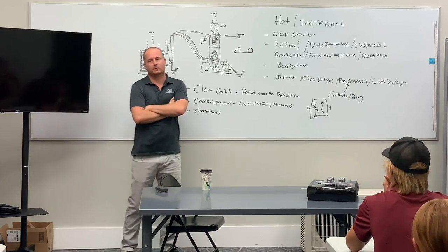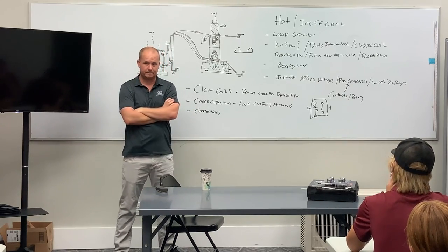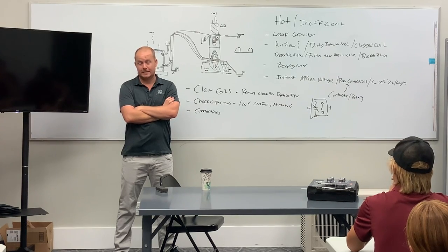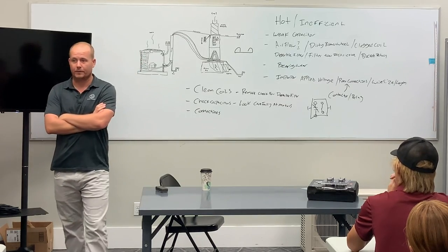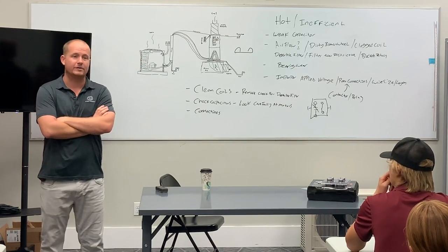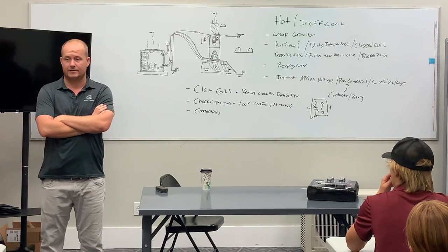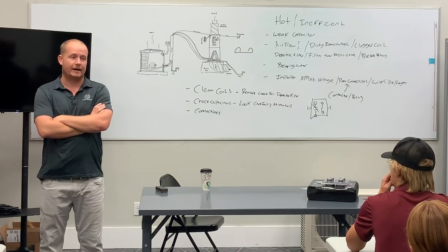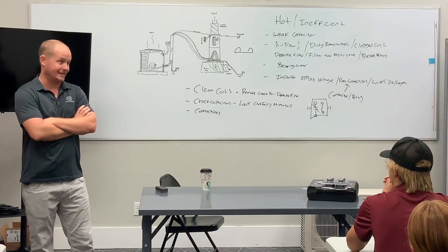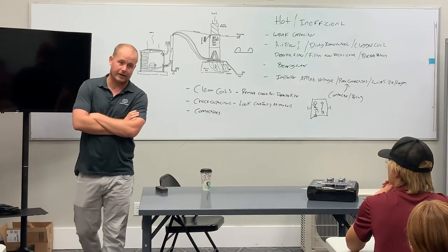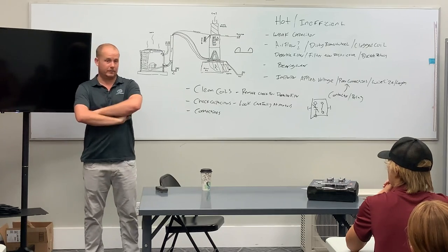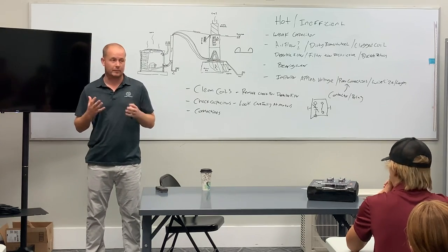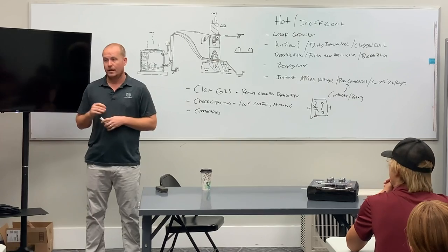All right, what's another place where poor connections show up a lot? Inside the air handler. That actually is a good one. It wasn't on my list, but it is a good one because there are a lot of really poorly made, field-connected terminations inside air handlers. Also within air handlers, just as a side note, a lot of really poorly routed wires, routed in such a way that they're going to get cut or damaged or get abrasions where they run through the cabinet.